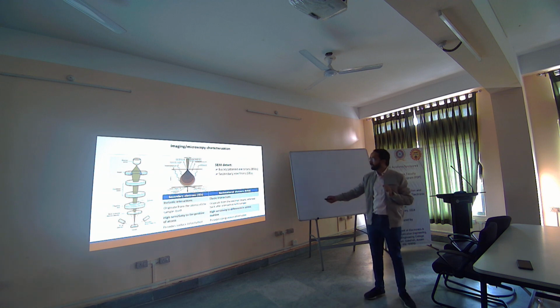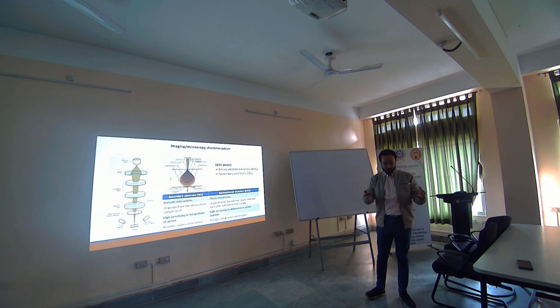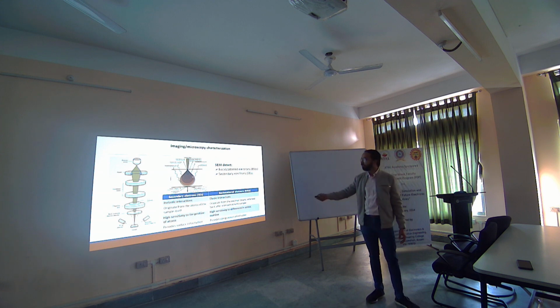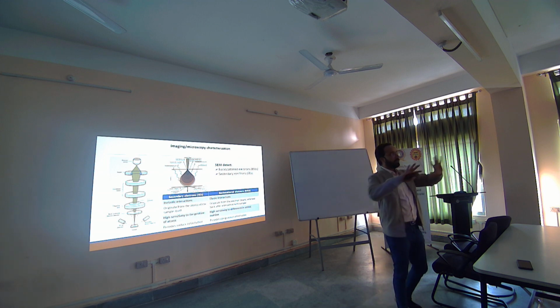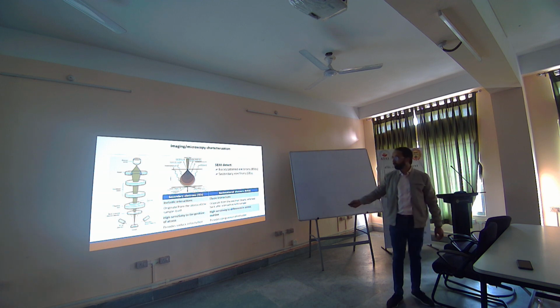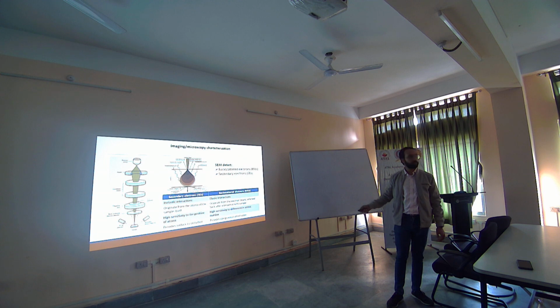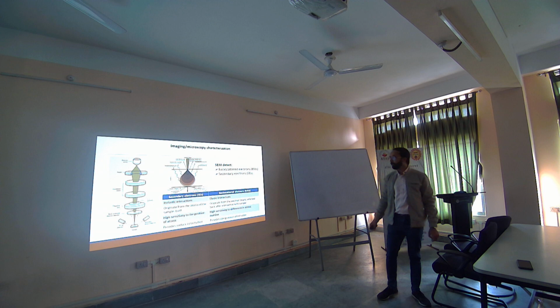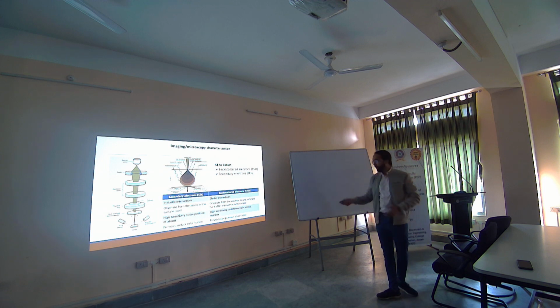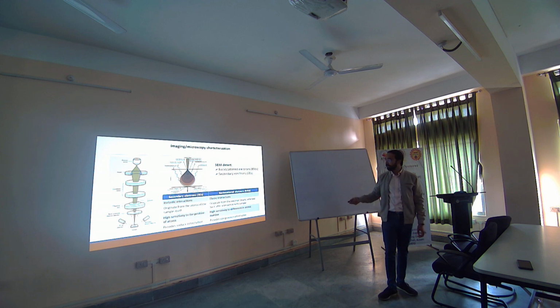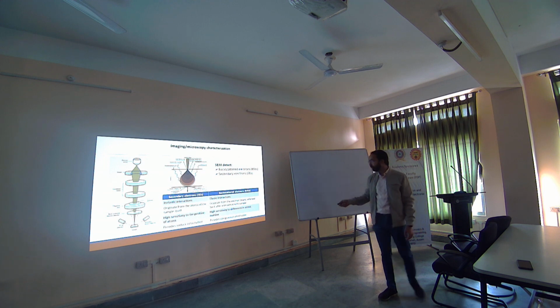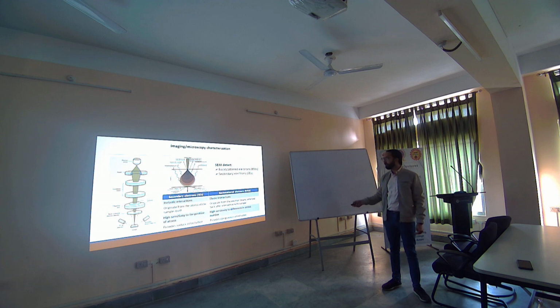Okay, so the secondary electron, as I told you, gives you more about the morphology, the structure; this kind of thing will come from the secondary electron. The Auger electron, which is coming from very near the top of the surface, is measuring more the composition and all those things. And then the backscattered electrons can also give you some information about the difference between two different materials. Now some SEMs are based only on secondary electrons, which come from the inelastic interactions of the incoming electron beam with the material. But some SEMs can also use backscattered electrons, which originate from elastic interactions, and they have high sensitivity to differences in atomic number. That's why I said you can differentiate between materials of different atomic number because of the backscattered electron.